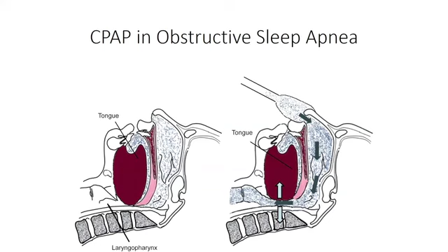And so with this donation of these ResMed bi-level devices, again, bi-level being different from CPAP in that you have the ability to increase the airway pressure above a set pressure, we were able to model this after pressure control ventilation, which is a standard mode of ventilation on our ventilators. In pressure control mode of ventilation, we increase the airway pressure and deliver flow for a set amount of time above the PEEP. With the bi-level machine, instead of a PEEP, we set our expiratory positive airway pressure, and then the IPAP is the total pressure in the system, the inspiratory positive airway pressure, with the inspiratory time.